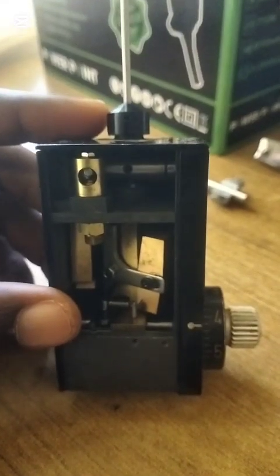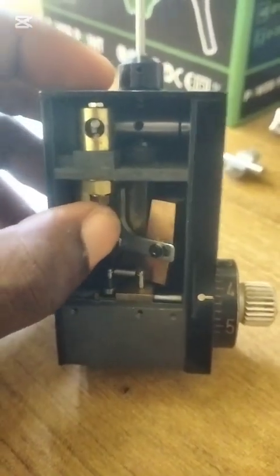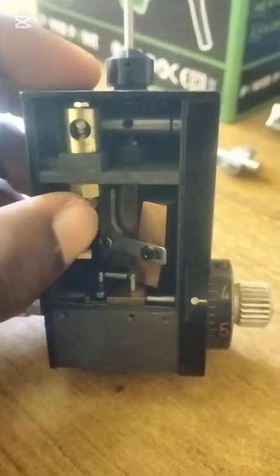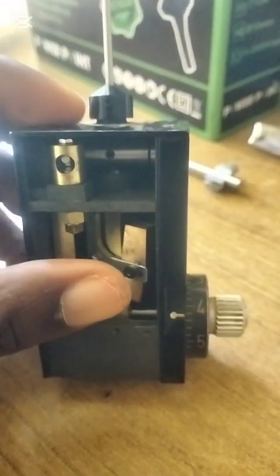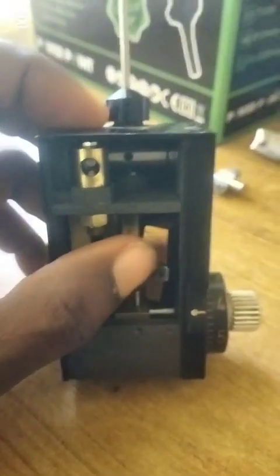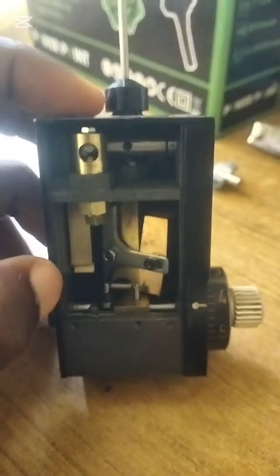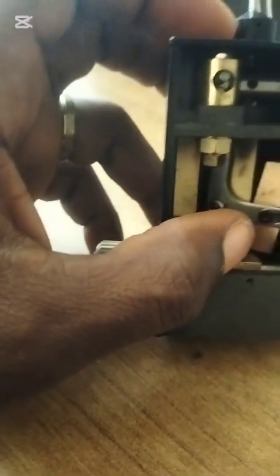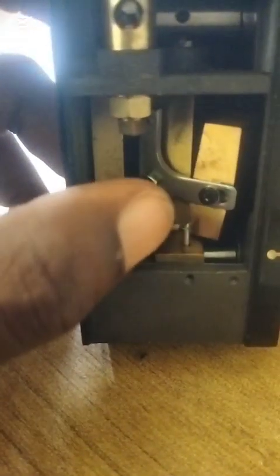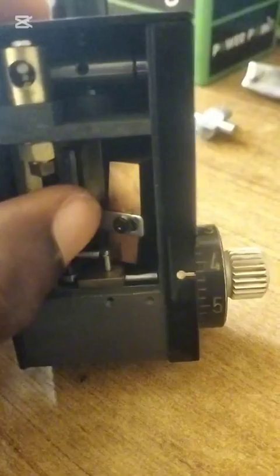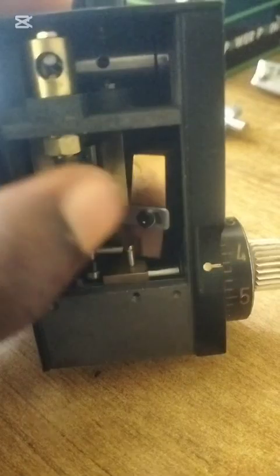Okay. Before we do that, let me also show you some other things you may encounter. So let's say you're doing the calibration, you're still having error margin. You just come and adjust this, that you tighten or you loosen. This will help in straightening up your calibration. Okay? You don't tamper with the weight. If not, you have ruined your tonometer and you have to get a new one. Then careful with the springs. So everything you tighten, you tighten. Either loosening this or you tighten this.